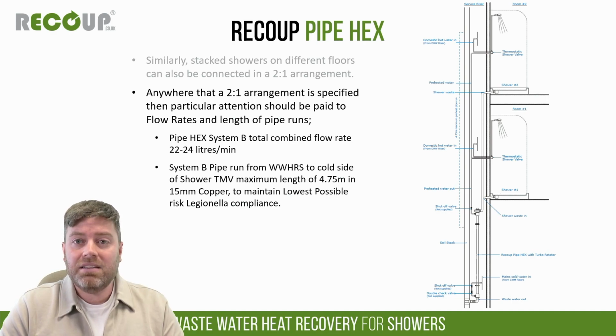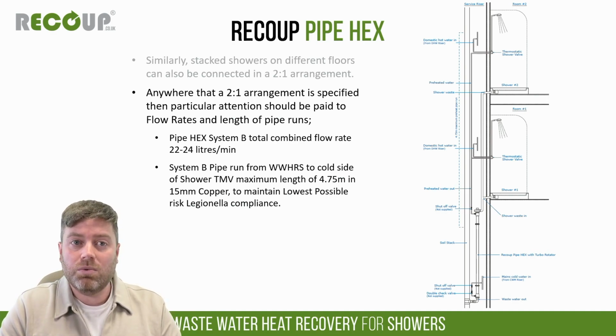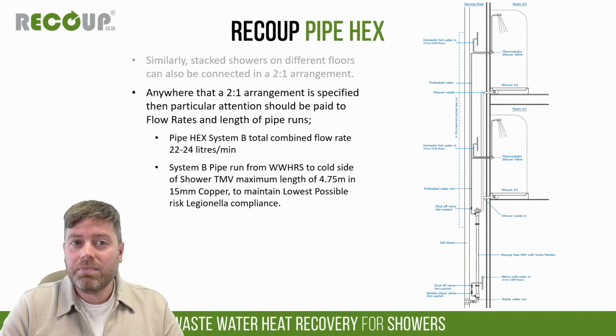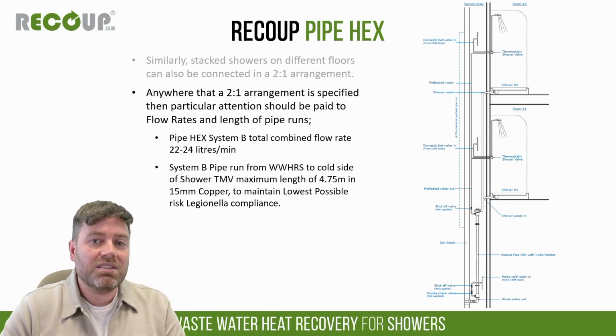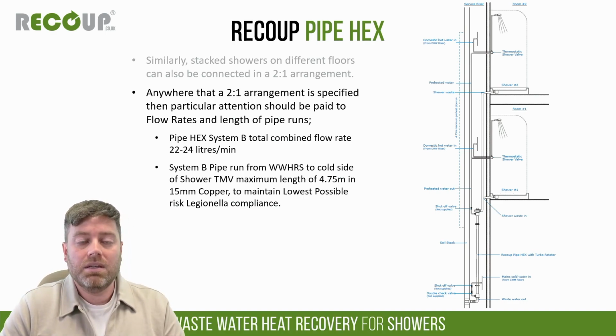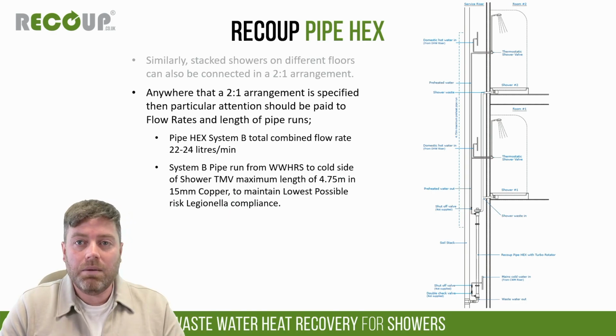The Pipe HEX on a System B install, which is typically what you'd see for, say, a hotel where you've got centralised hot water, is sort of 22 to 24 litres per minute. So you can still get 2 quite nice shower flow rates connected to that, and have no problem with a limitation on flow. There is a limitation in terms of the maximum pipe run you can have from the preheat out of the wastewater heat recovery unit to the connected shower. So when the preheat pipework leaves the wastewater heat recovery unit and goes up to the cold side of the shower mixer valve, that length must be no longer than 4.75 linear meters in 15 mil. That's a Legionella measure, so that maintains the lowest possible Legionella risk compliance. It means the volume of water held in the pipework is minimised.